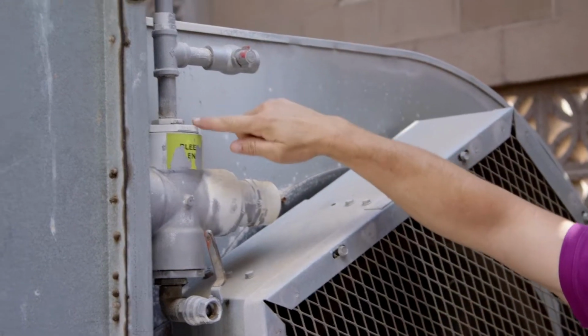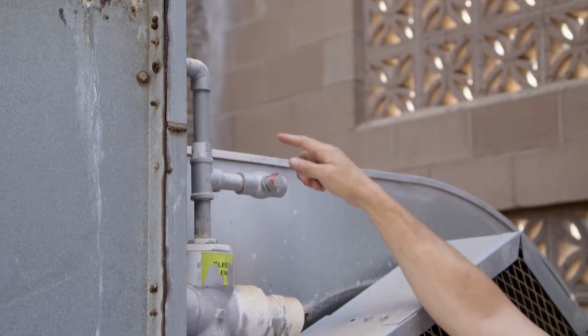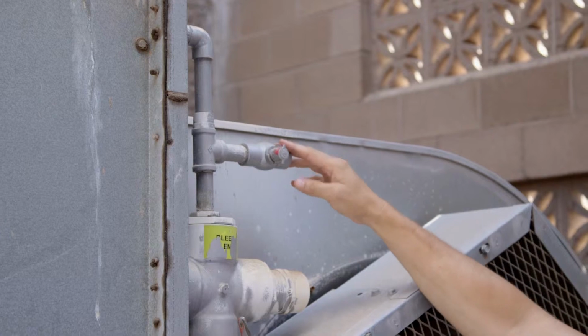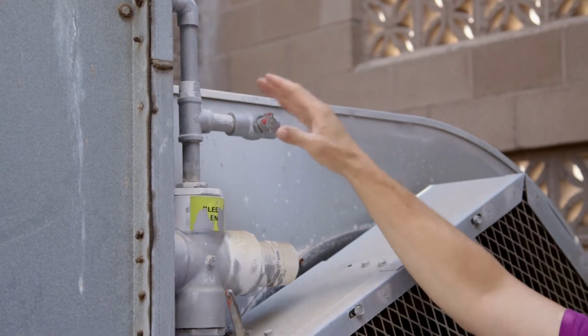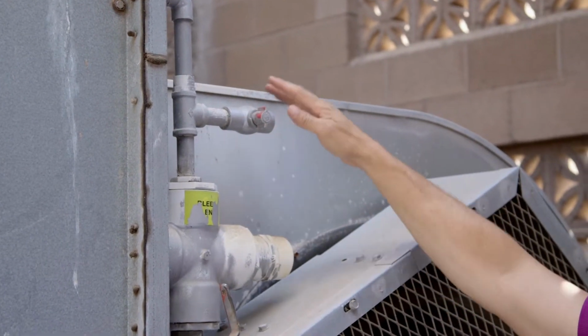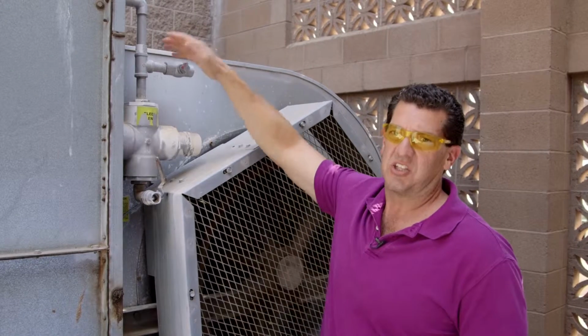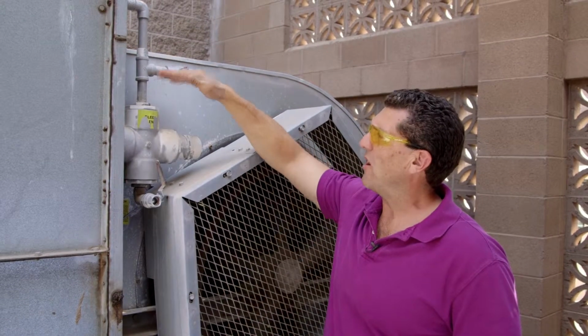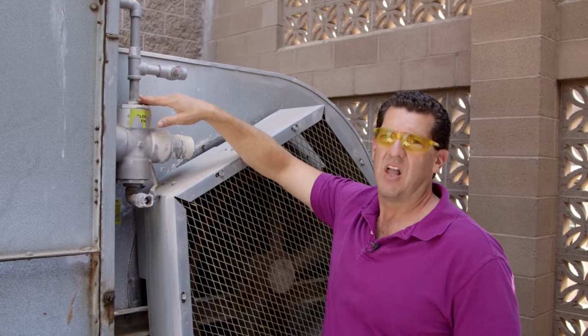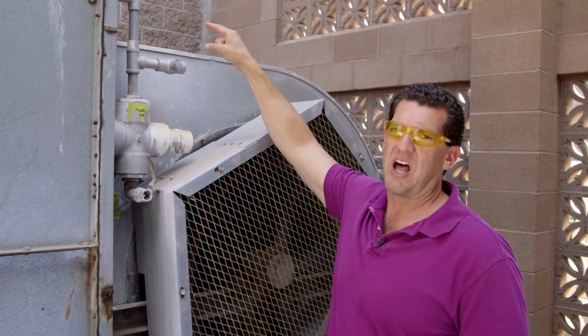So a dead leg on this line is the end of the distribution header, and the last treatment company that was here before us had their line going down to the other side, but it dead legs. It doesn't go anywhere. So this really should be capped off, cut right here. I'm going to take you to the other side and show you where that line goes.